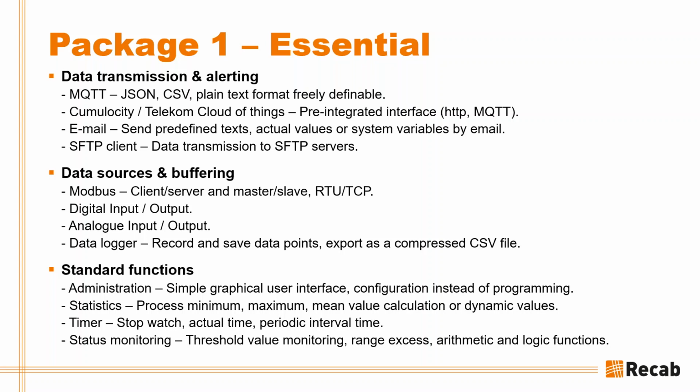You are able to get statistics, get the minimum, maximum, or mean value calculations, or even dynamic values. You have the timer function with the stopwatch time and periodic interval time. Say you want something to happen every day at 4 o'clock, then you can set that in the periodic interval time. And you also have the status monitoring with the threshold value monitoring and range excess. You can do arithmetic and logic functions, so you can take in data and process it in the router before you send it further.